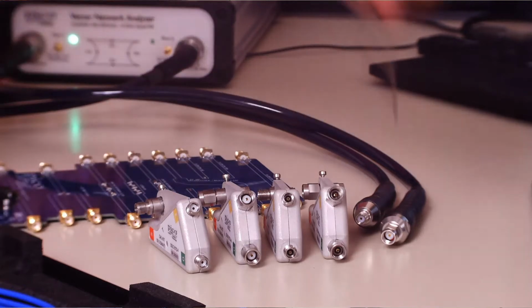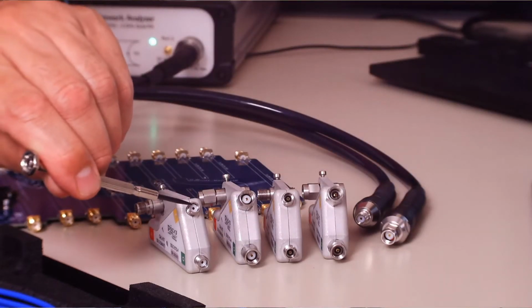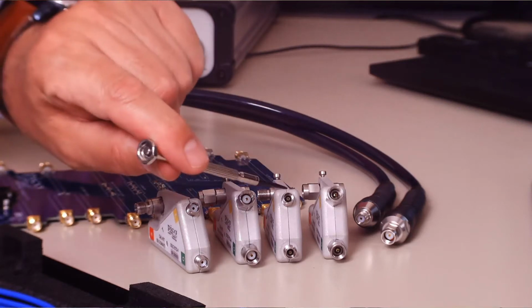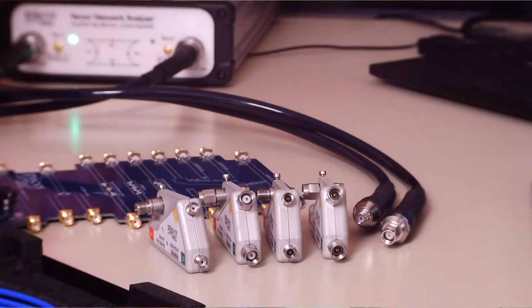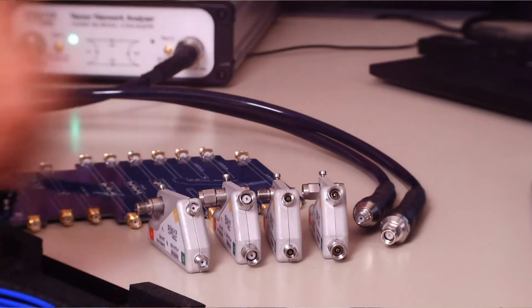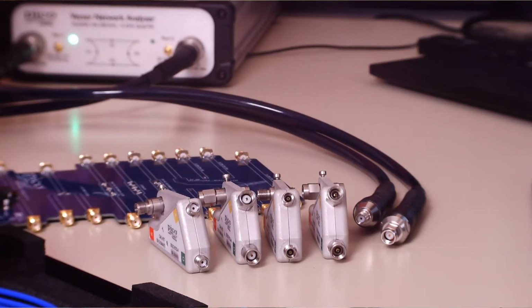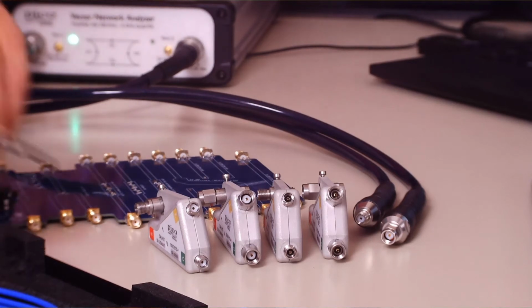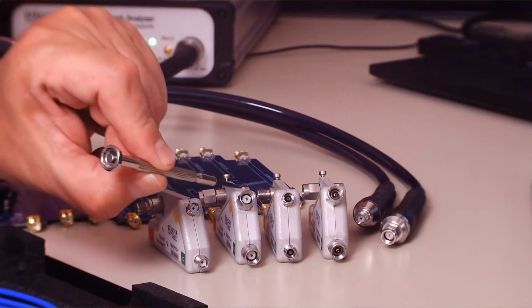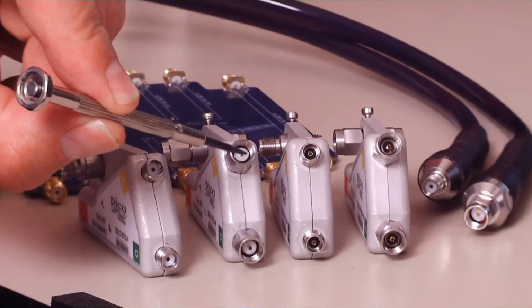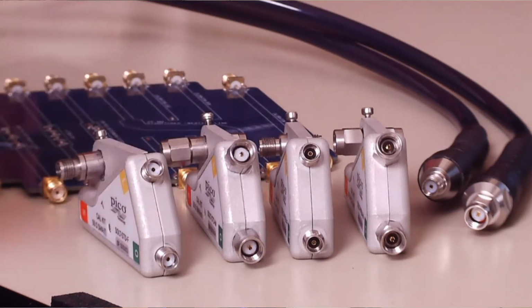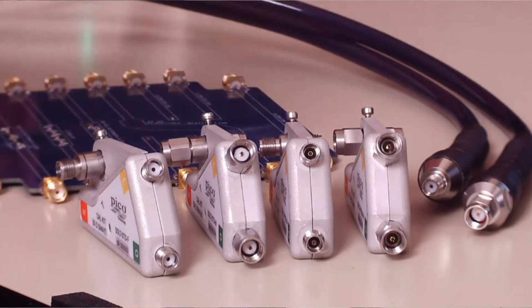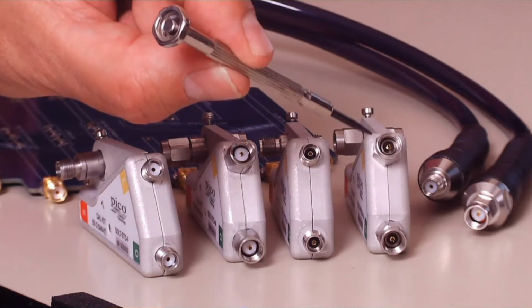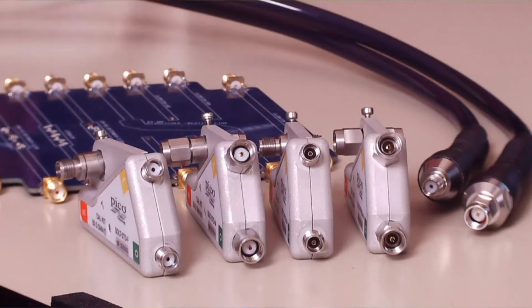When I'm looking at an SMA connector, I know this because you can see in here there is a white dielectric, whereas a PC 3.5 has an air dielectric. So there's some degree of uncertainty associated with that white dielectric there, and variability between connectors. But perhaps more important, when we have some dielectric material in connectors that are essentially the same dimensions, a dimension has to change, and you will notice here that the ring that forms the reference plane, that ring of steel around the white dielectric, is quite thin, whereas on this one, where the air is forming the dielectric, we have a much thicker ground ring.